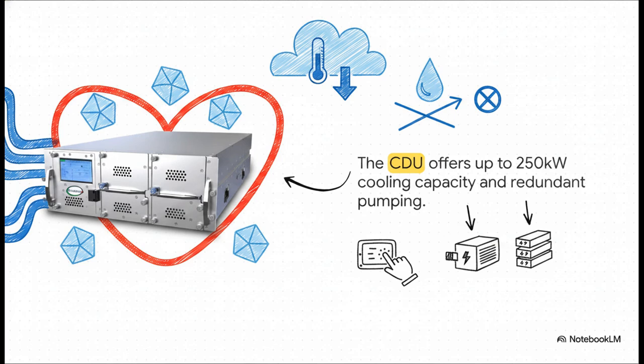So all of that plumbing leads right back to the coolant distribution unit, or the CDU. This is really the powerful beating heart of the whole system. Depending on how it's configured, a single Supermicro CDU can pump up to 250 kilowatts of cooling capacity throughout the entire rack. Plus, it features hot-swappable, redundant enterprise-grade pumping and power modules, so if something fails, the system stays up. Operators can even use an integrated touchscreen to monitor and optimize power consumption, all while managing a smart anti-condensation strategy to prevent hardware degradation.